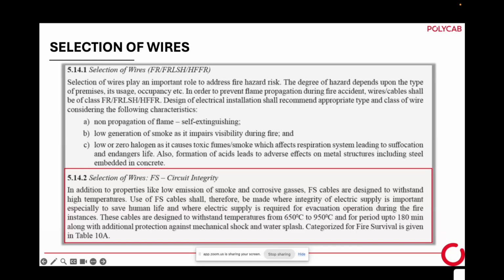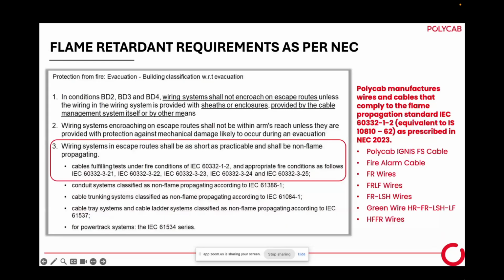I think we should follow this, so this kind of accident may not happen. Another thing - NEC clarifies that whatever fire retardant cable will be there, they should comply with IEC 60332-3-21, 22, 23, and so many tests. This gives you a test - even if there's a fire and the cable catches fire, at a heavy temperature of 750 or 800 degrees, after withdrawing the temperature, how much unburned portion will be there - that shows the testing.